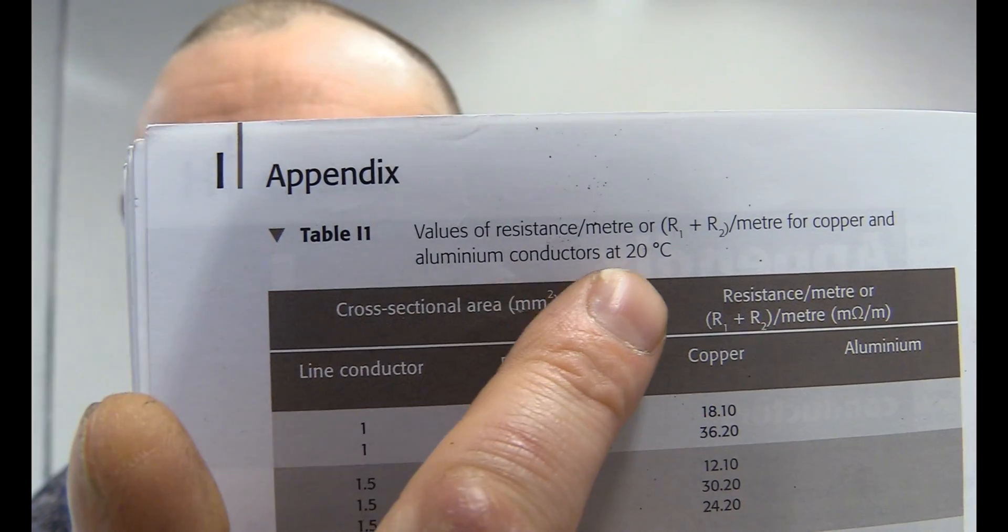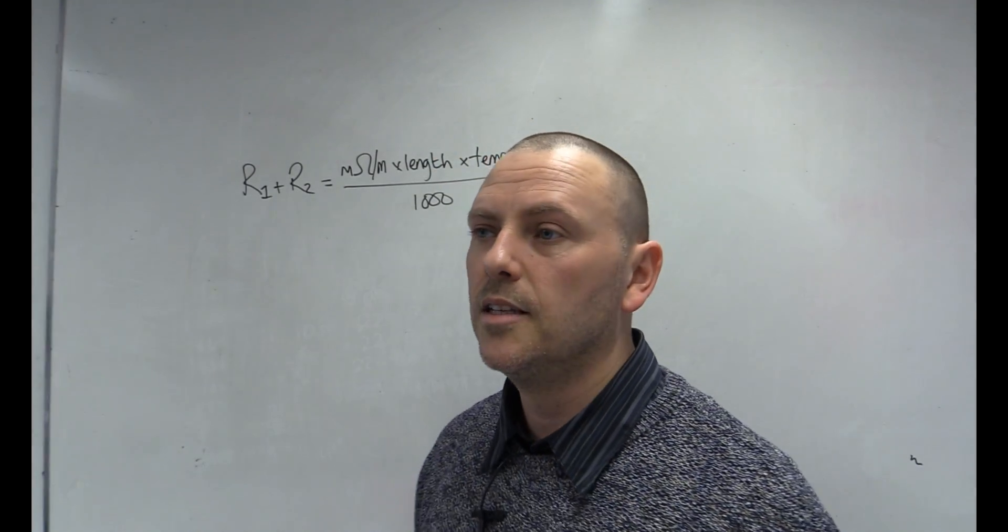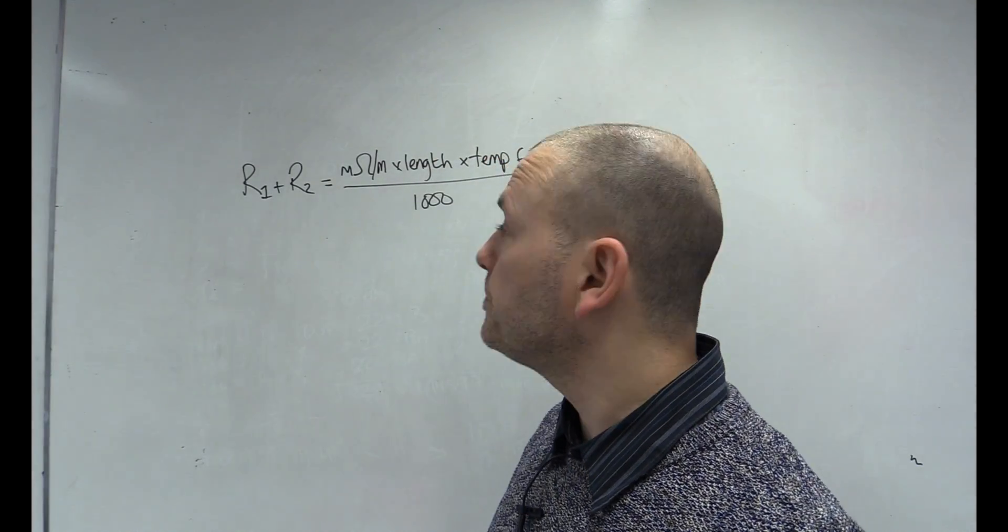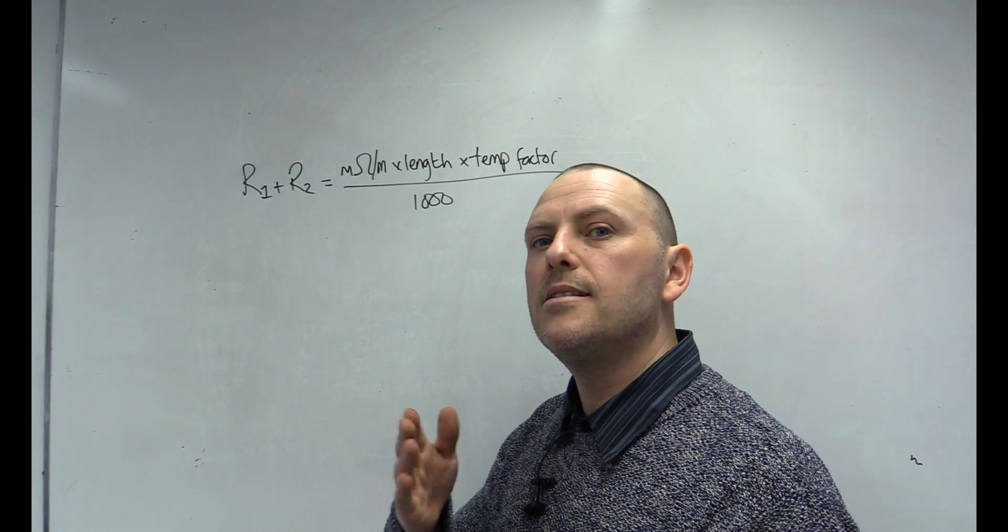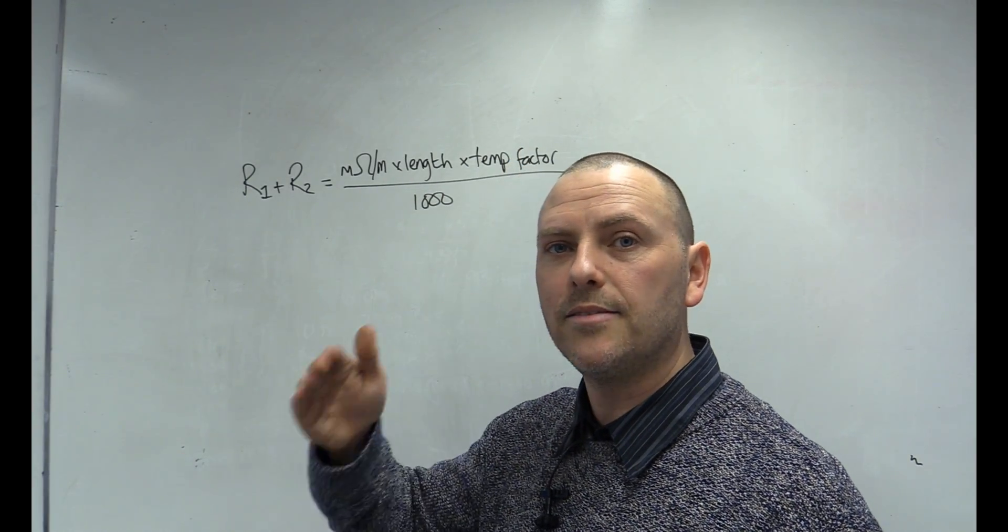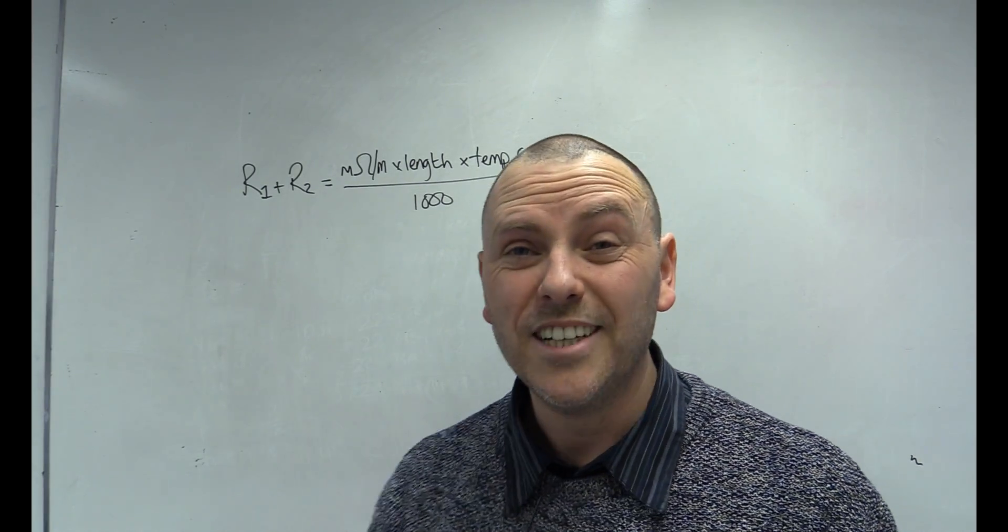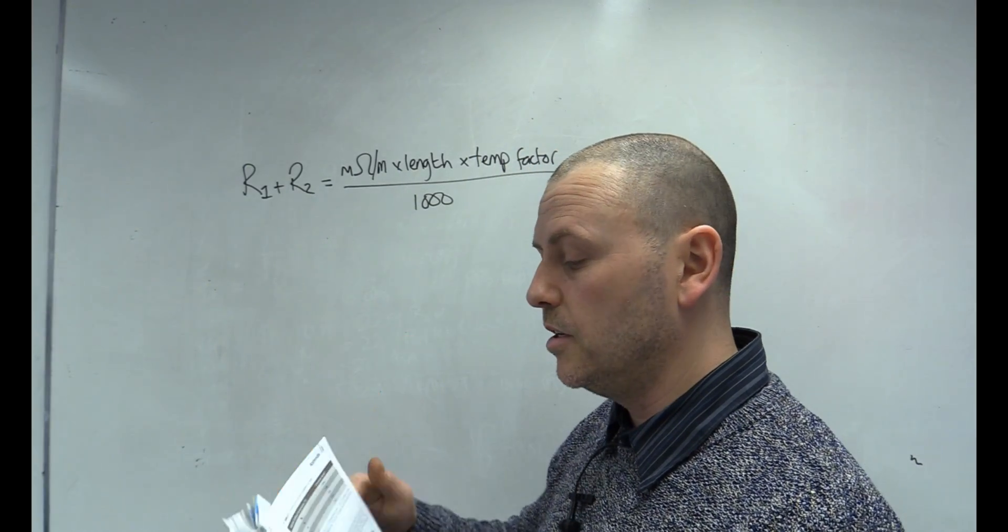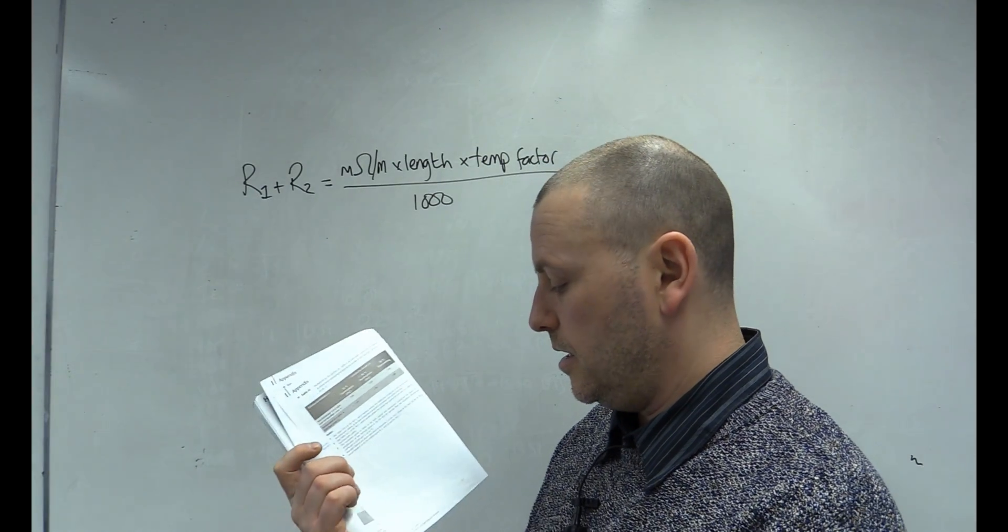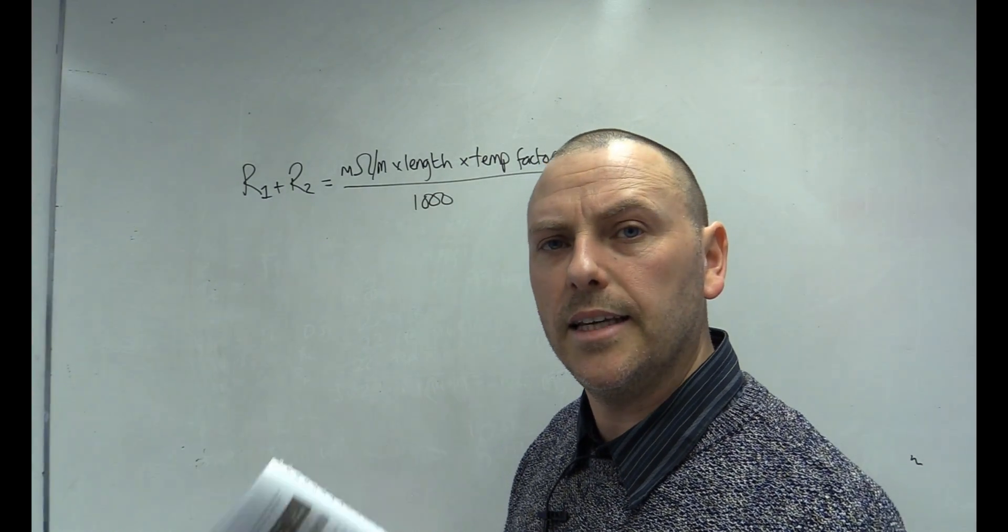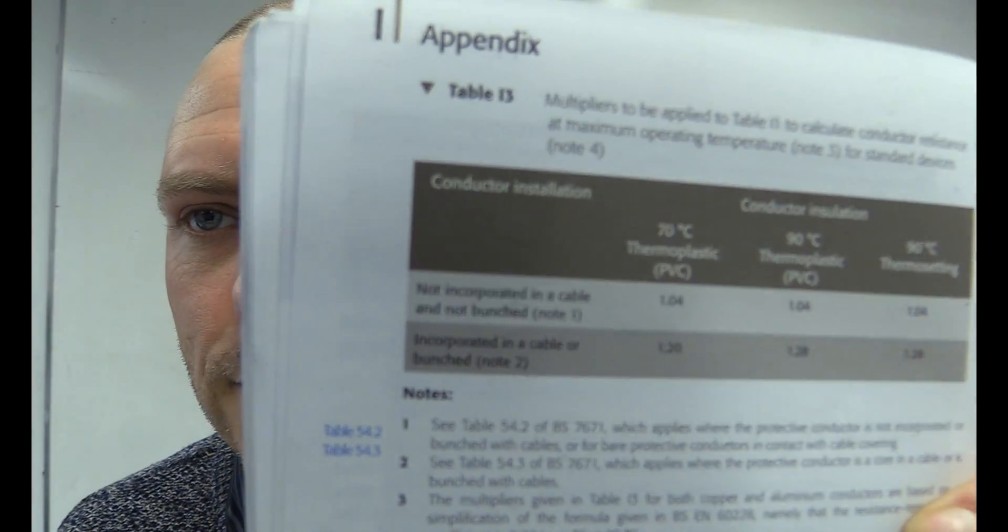Now, just notice that this is at 20 degrees, and so the maximum operating temperature of, say, a thermoplastic cable is 70 degrees, thermosetting cable 90 degrees, and so there's different factors to get to the limiting factor of those cables. They've made it really easy. They've given you another table. It's just one page away. Table I3, currently page 198 in the 18th edition on-site guide.